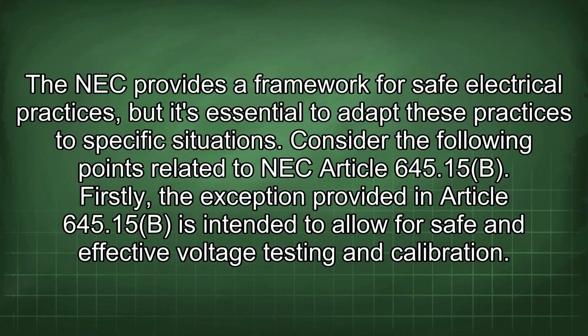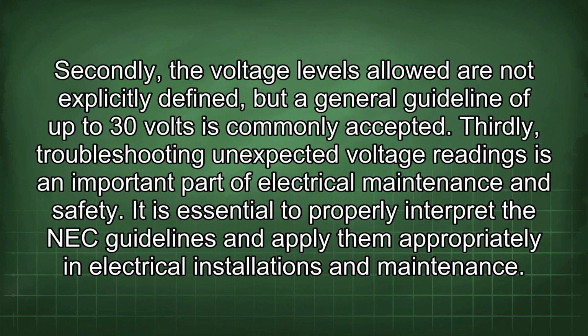Consider the following points related to NEC Article 645.15(B). Firstly, the exception provided in Article 645.15(B) is intended to allow for safe and effective voltage testing and calibration. Secondly, the voltage levels allowed are not explicitly defined, but a general guideline of up to 30 volts is commonly accepted. Thirdly, troubleshooting unexpected voltage readings is an important part of electrical maintenance and safety. It is essential to properly interpret the NEC guidelines and apply them appropriately in electrical installations and maintenance.